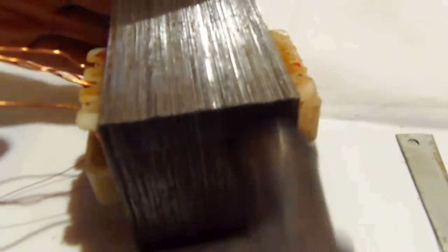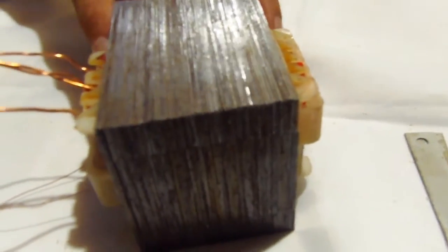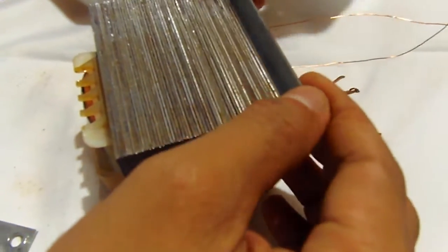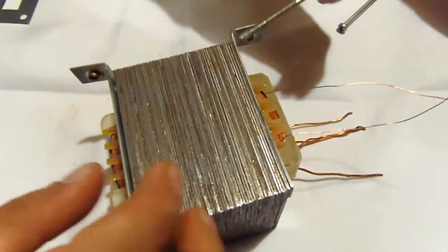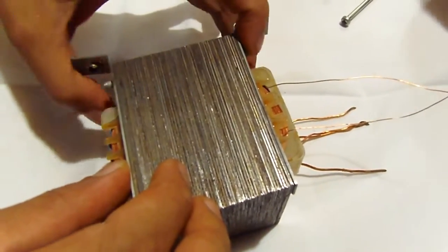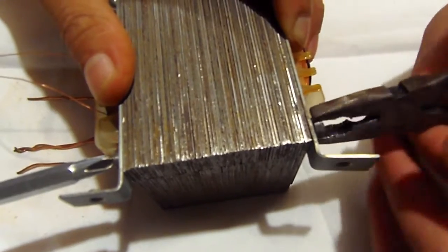Rigid bracing is always important in transformer assemblies. Unless this is properly done, the laminations and coils will vibrate with the current changes, and thus cause objectionable noise, a humming sound, and even insulation failure.